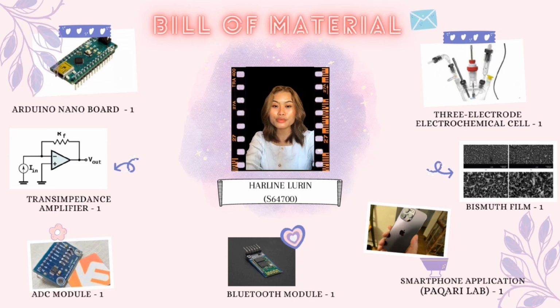Next, we have the Bluetooth module, a wireless connection that transfers the real-time digital signal from the ADC module to a smartphone application, establishing a connection between the potentiostat and the smartphone. This system also includes a smartphone application, Paqari Lab. The application controls the potentiostat and receives data. It is compatible with Android 7.0 or higher. The application allows method selection, parameter input, and real-time data display.